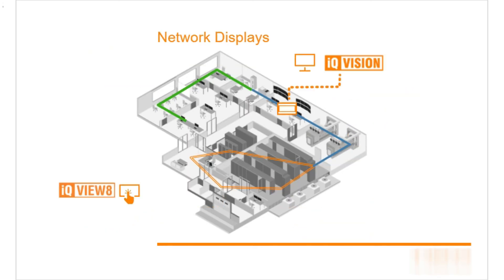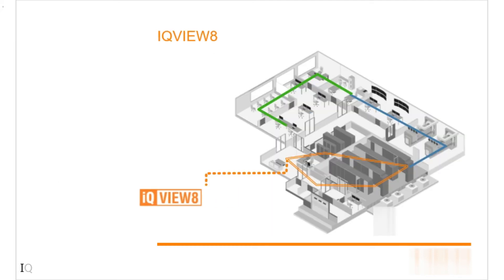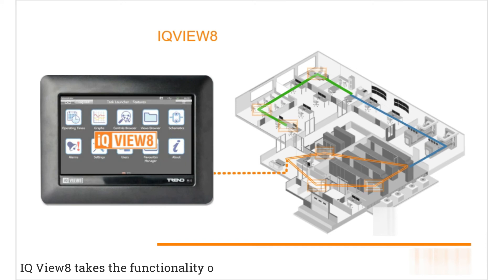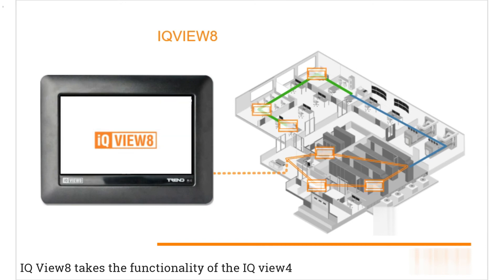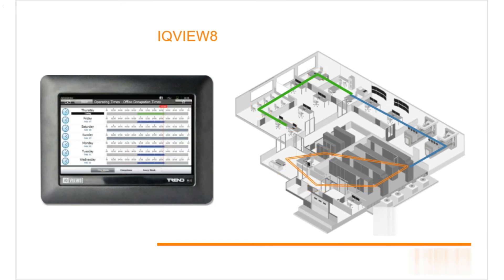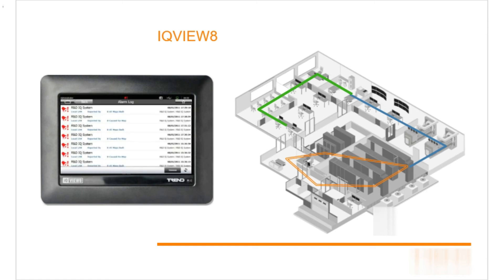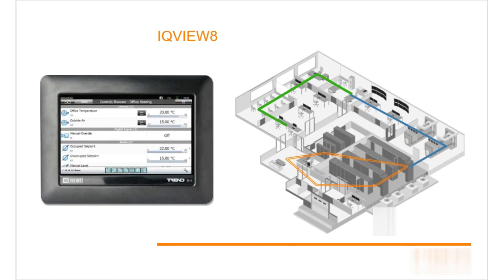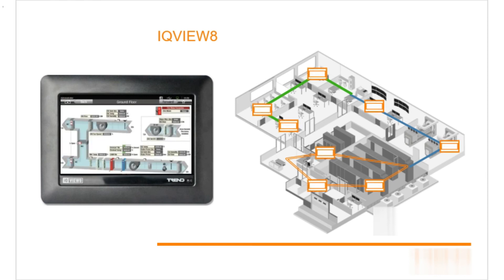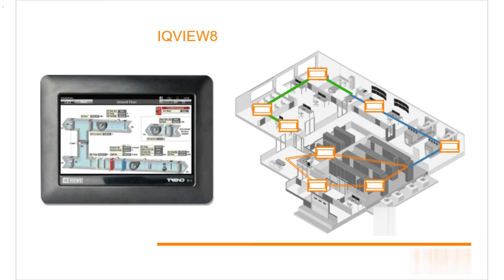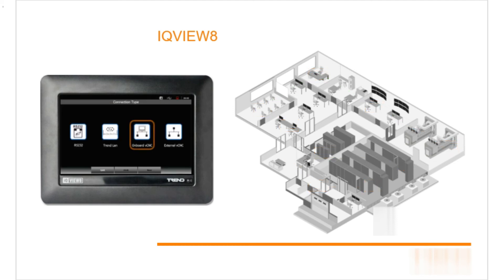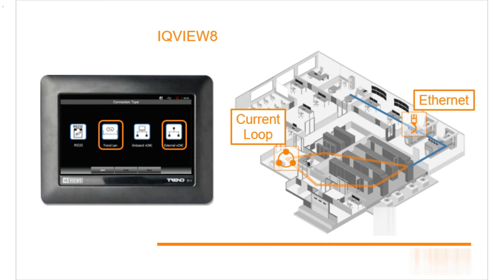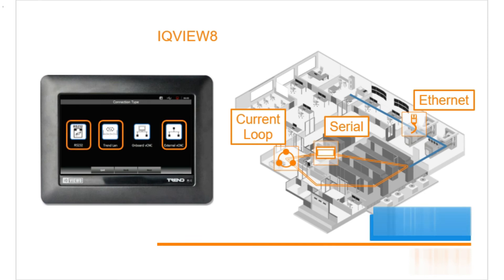The iQ Vision supervisor and the iQ View 8 are network displays. iQ View 8 takes the functionality of the iQ View 4, but for any controller on the site. It is also possible to have graphics pages with specific information created to make finding often requested information simpler and faster. iQ View 8 can see any trend control on the site. It doesn't need to be connected to a specific controller and so has its own CNC and both current loop and Ethernet network connections, in addition to being able to use an RS232 supervisor port connection.